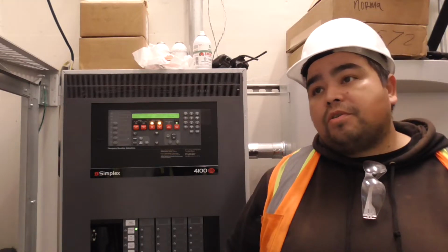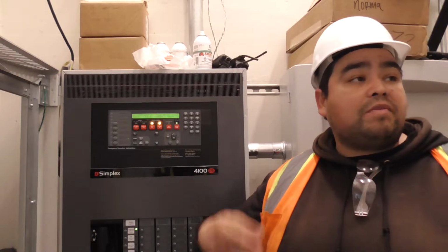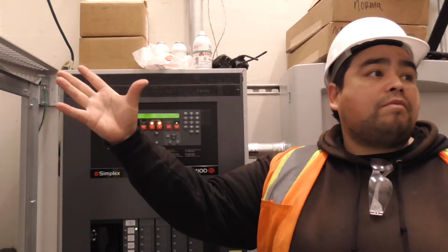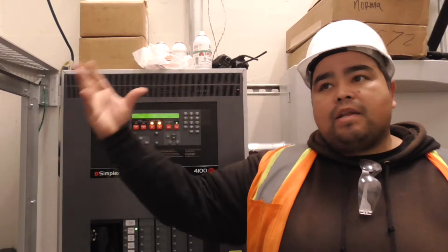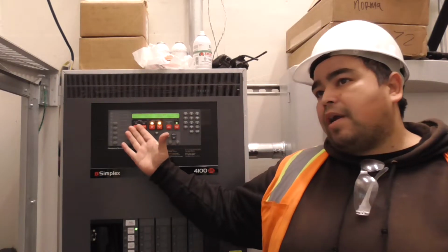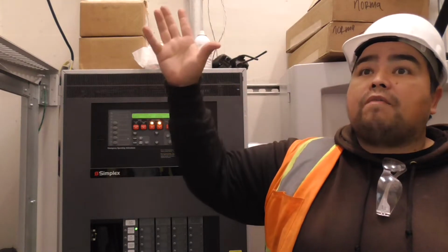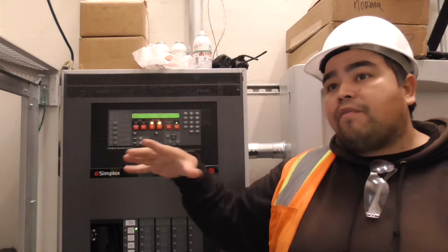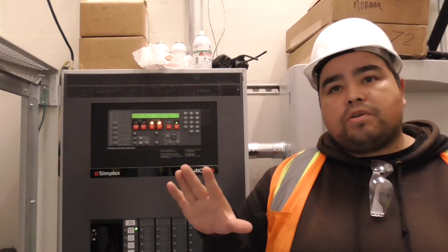There's really no issue, but if somebody sets the same detector off again, it won't re-alarm itself. It's the same thing with an alarm event. So let's say I set off a smoke detector in this room, it's a general alarm. I silence the building, everything's off on silent. When you hit silent, it turns strobes and speakers off, everything.